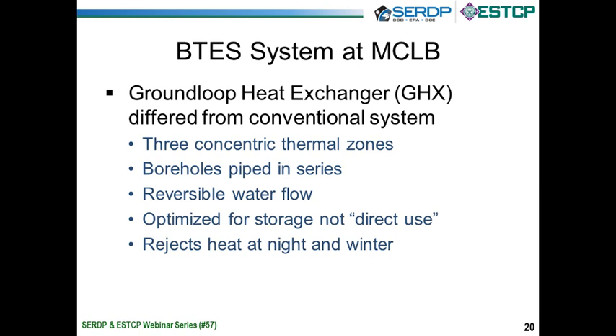Most American designed systems are designed for what Europeans call direct use. We want to use the ground as a heat sink and a heat source, but we're not really optimizing it for storage. In fact, storage sometimes inadvertently becomes a problem because heat builds up at the core of the bore field and we can't get rid of it if you're a cooling dominated system. So BTES is different in that we are using the geology certainly for heating and cooling, but beyond that, we are optimizing the design of the ground loops for storage purposes.